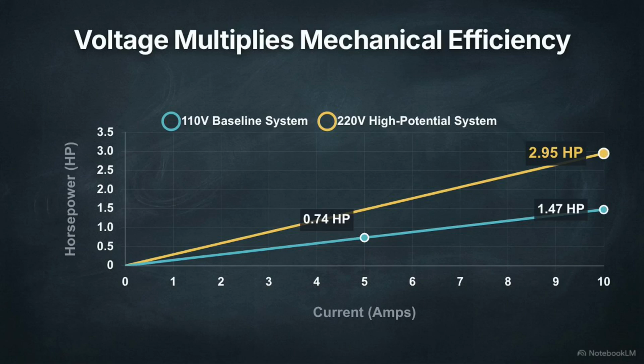We trace that same 10 amps of flow through the new 220-volt system, and our digital readout leaps from 1.47 horsepower all the way to roughly 2.95 horsepower. And that phenomenon right there is the core insight of the entire source document. They call it slope sensitivity.